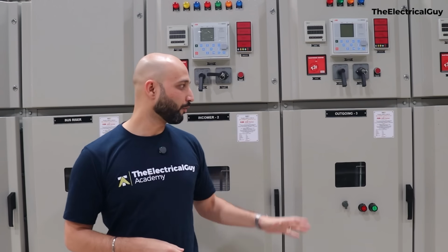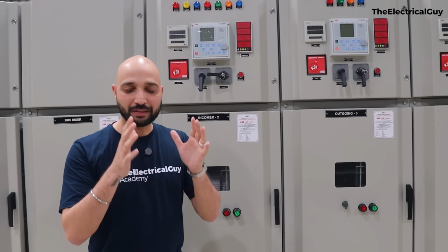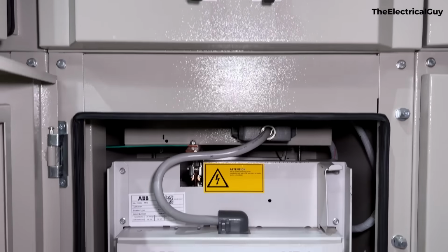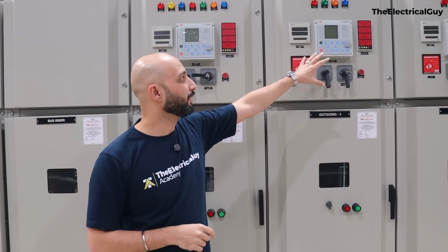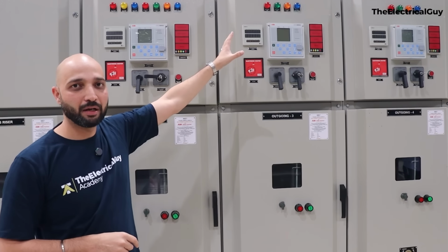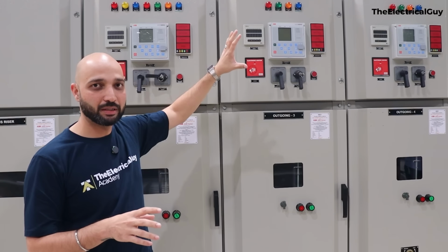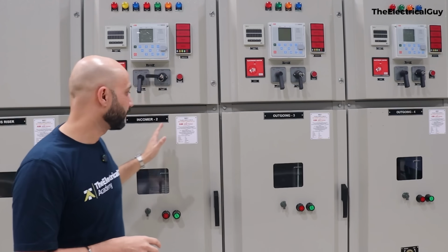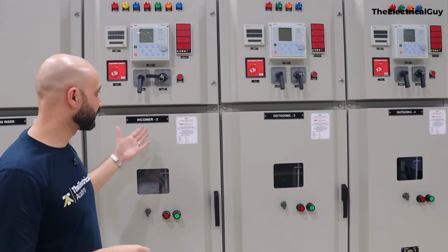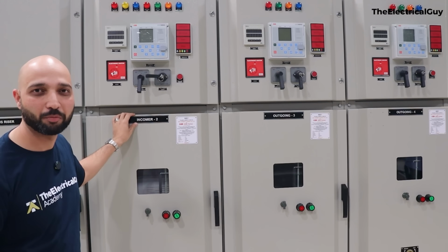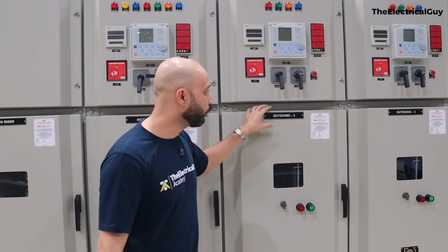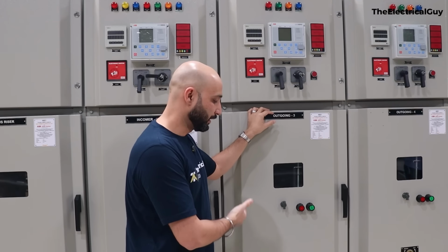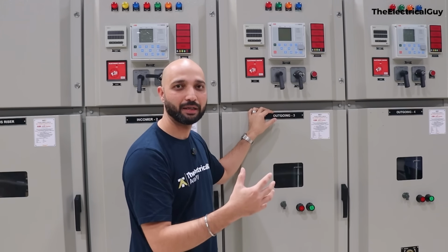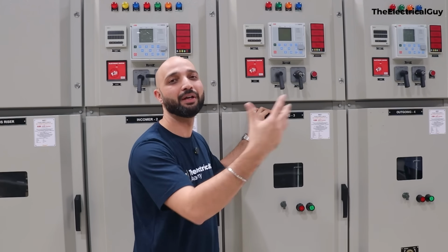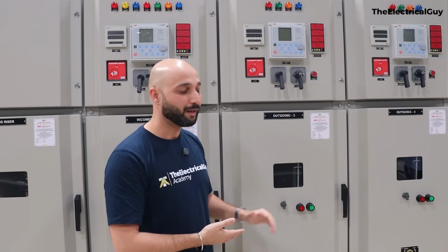So we have seen the overview of what we have in the Incomer 2 panel. The same identical equipment and apparatus you will find in Incomer 1 as well. Now going back to our outgoing panel, you will see the same relays, same functions, maybe some indications are different, but more or less you will find the same apparatus. Now why do we call it outgoing or, let's say, incomer? The reason is pretty simple, that we are accepting supply in this particular panel, which may be, let's say, coming from a substation or any other side. And then we have outgoing because this is also called a feeder, because this panel will help us feed the supply that we have, or feed another factory that we are going to, or feed any other substation that we are providing supply to. That's why its name is outgoing.